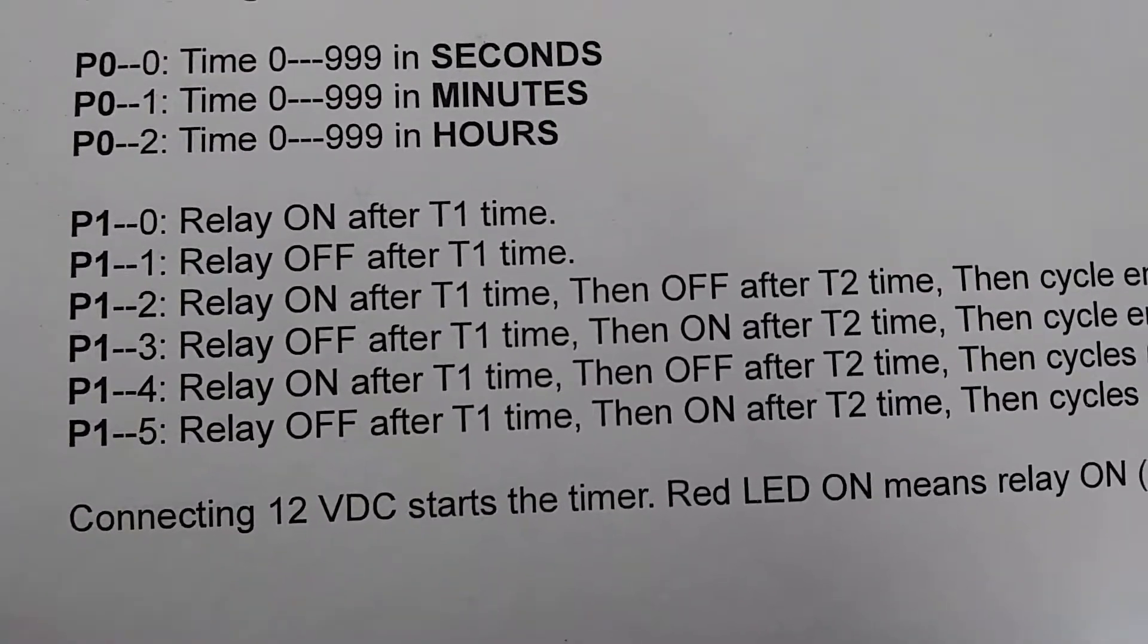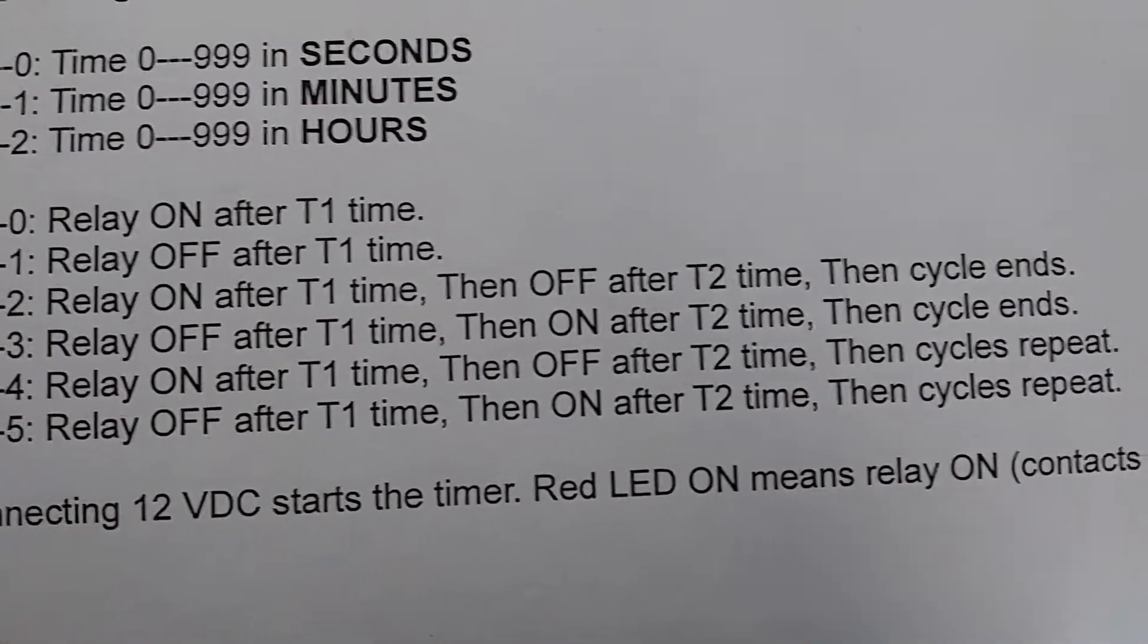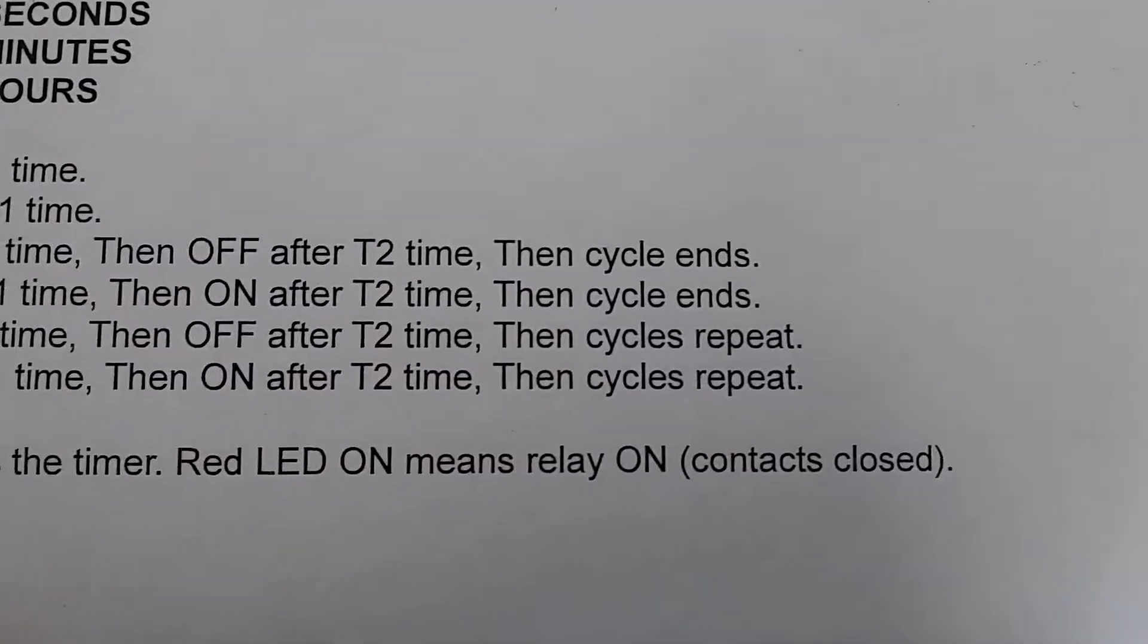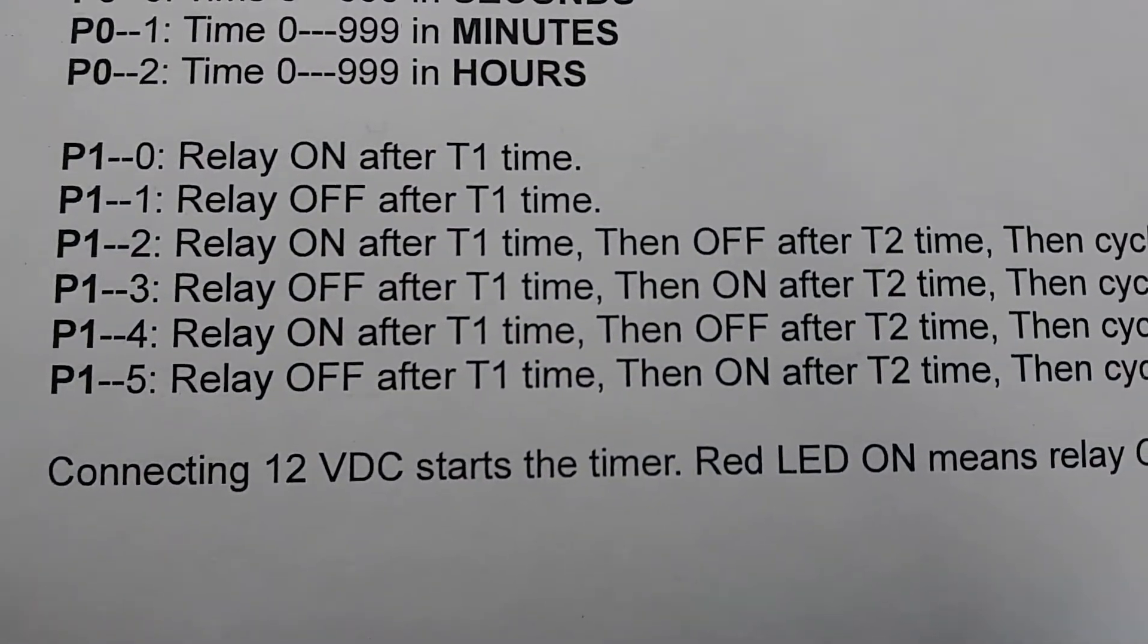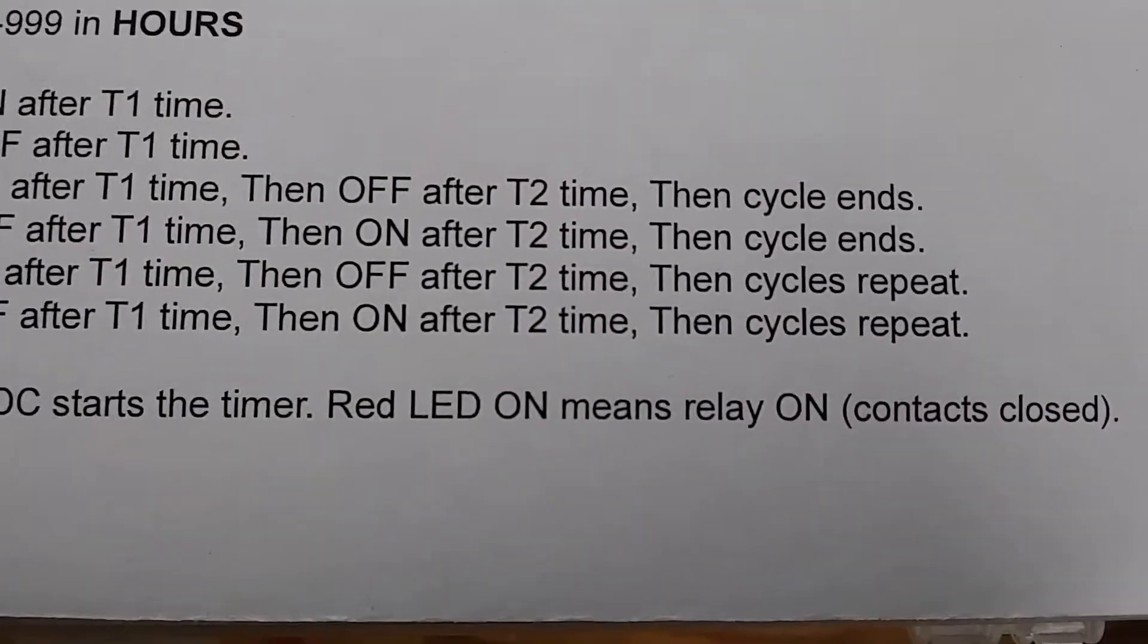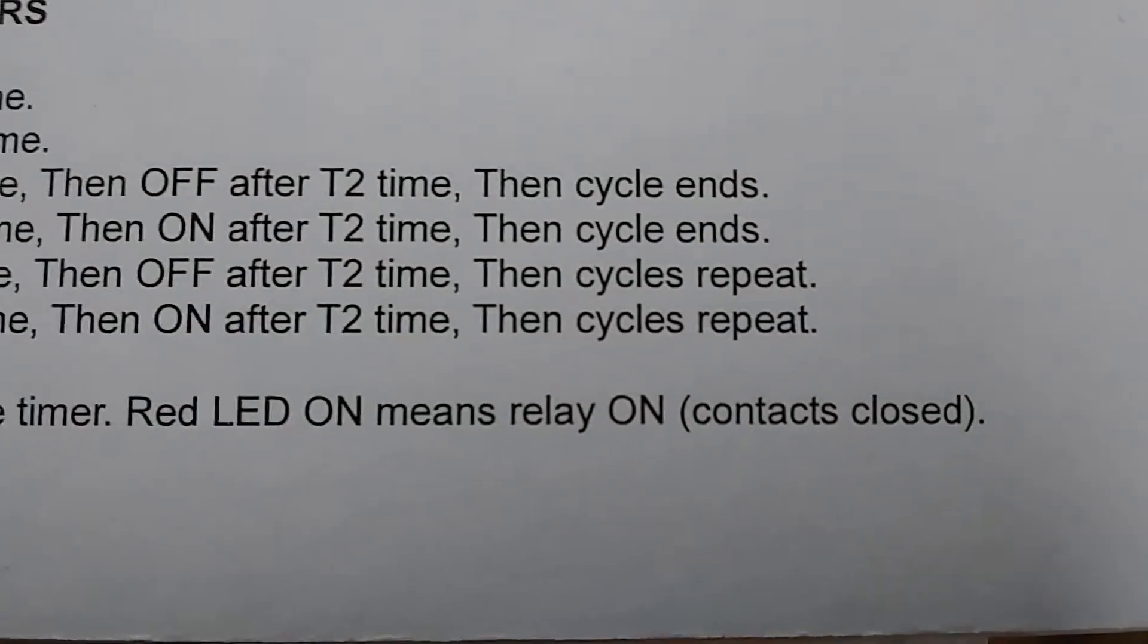Then we have the following option: relay on after T1, off after T2, which is the bottom line on the display, and then the cycle stops. And we have the same, but the reverse. The relay will go off after T1, on after T2 time, and the cycle stops. And then we have the same options, but the cycles will repeat.